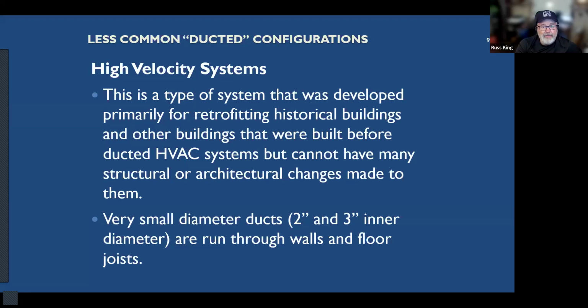There's another type of system called high velocity systems, or small duct high velocity. What they're basically doing is using little small ducts because of the challenge of running ducts through a house. Someone said, you know what? Let's just use small ducts and we'll use a really, really strong fan and force the air through these little tiny ducts. They actually invented this for historic buildings when they wanted to add air conditioning without having to modify the building too much. So they said, let's have these little 2 inch and 3 inch diameter ducts, but we're going to use a really strong fan and cram air through these ducts, and the air is going to move really, really fast. So they call it high velocity small duct systems. They work pretty well, but they require a lot of fan energy to do that.